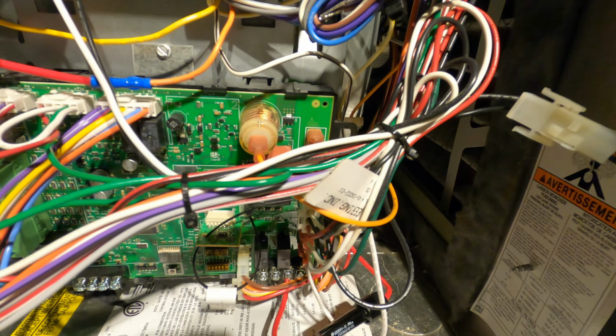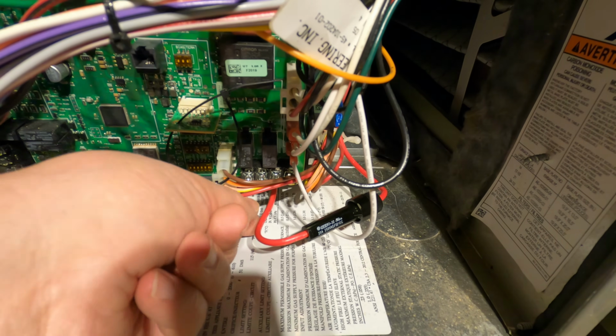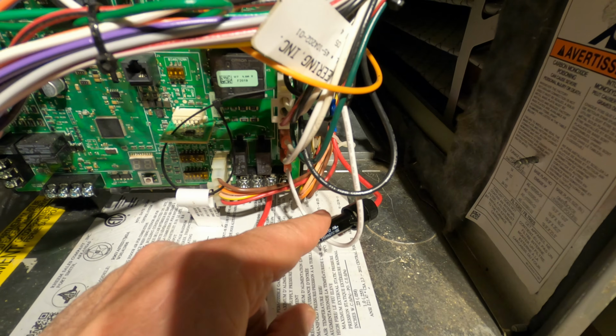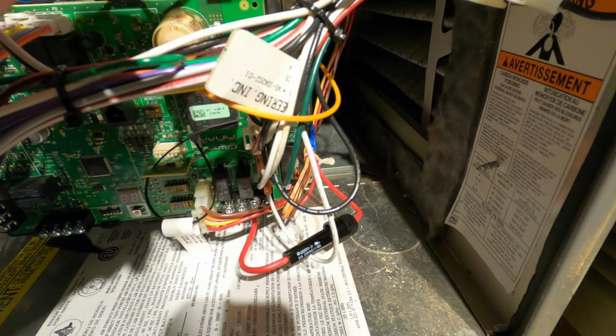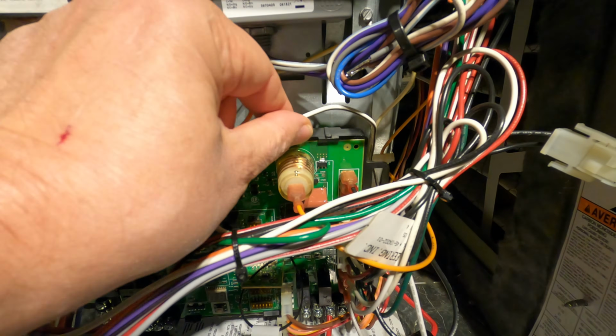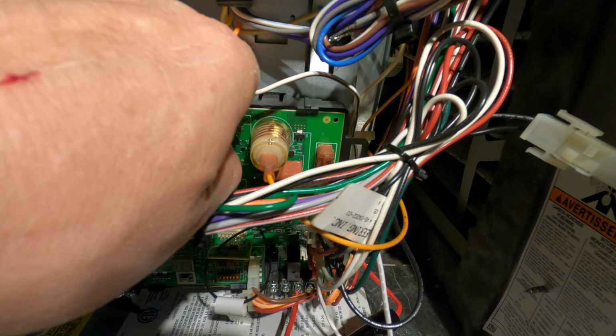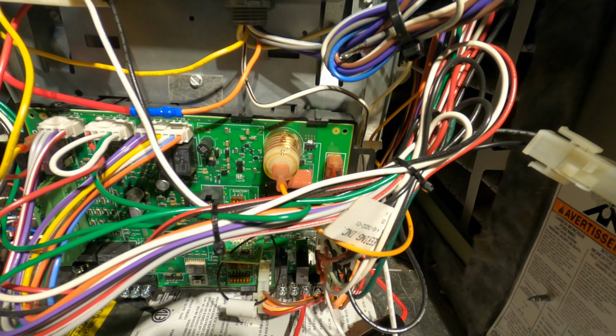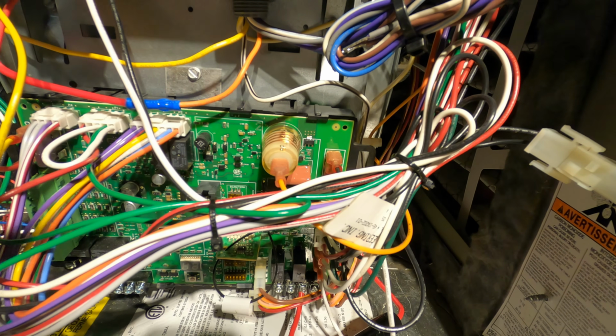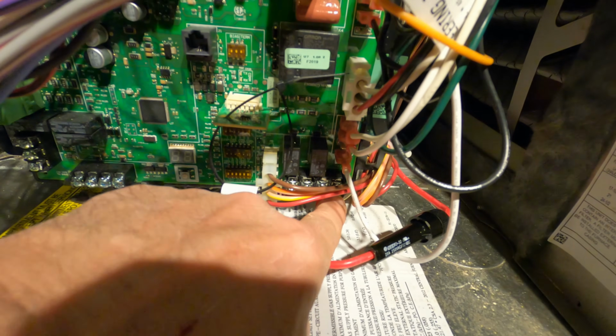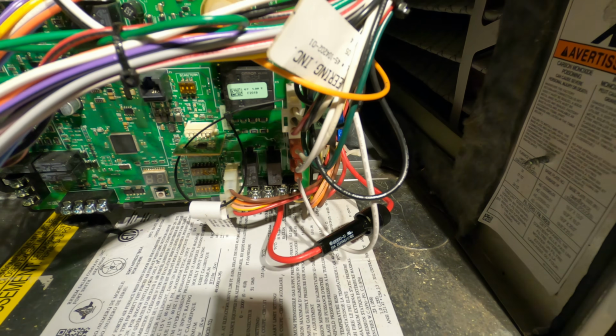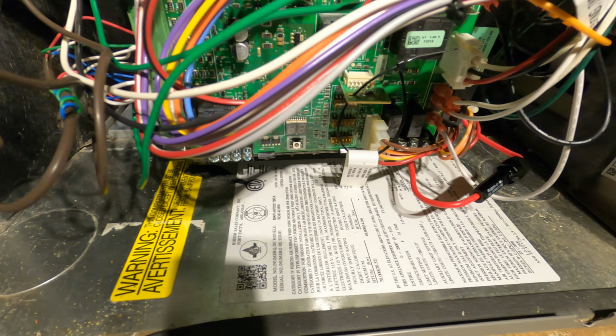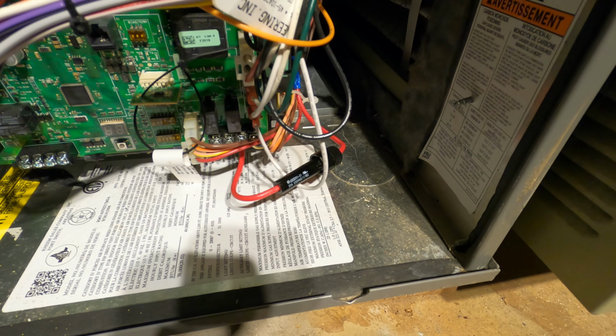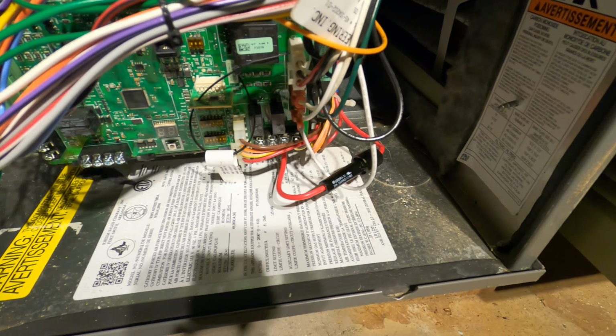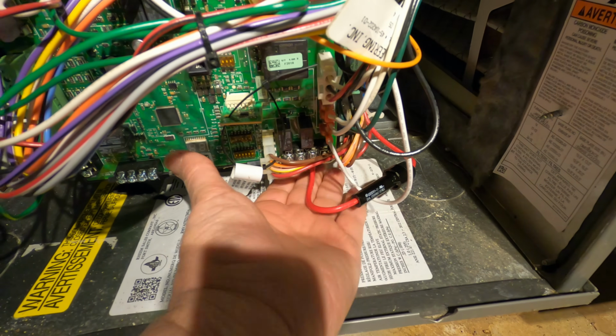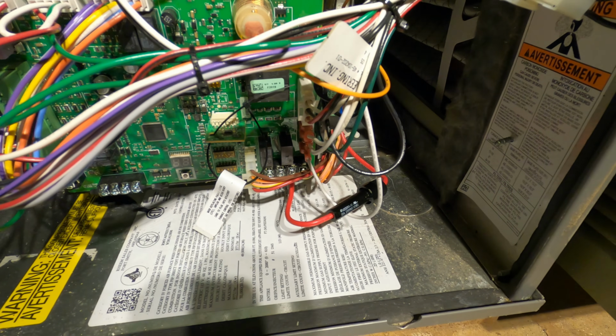Down here, the EAC signal comes out here, protected by a fuse, and that goes up, and it's spliced to this wire, which is the hot side of the coil in the relay. And then the neutral side of the coil is just run down there and terminated where it was originally. So now there's nothing laying on the bottom of the furnace to get wet in case there's another event where something's dripping down. There's a good bit of clearance here, more than ½ inch.